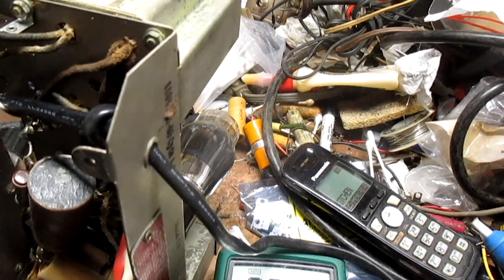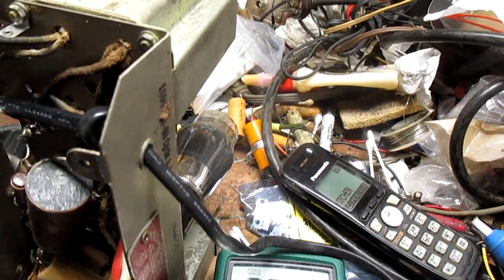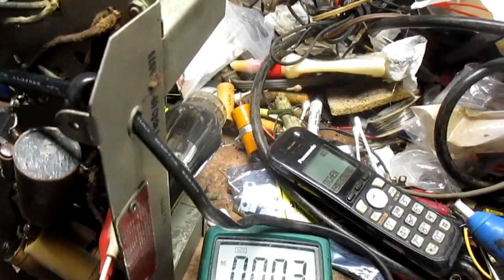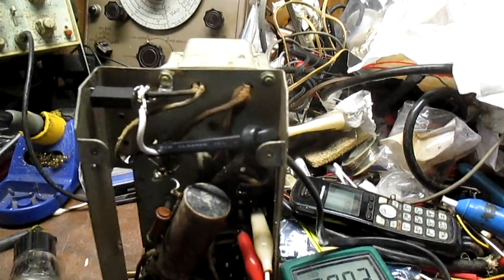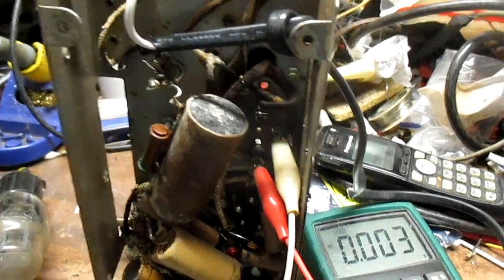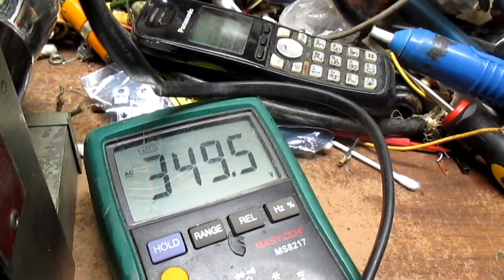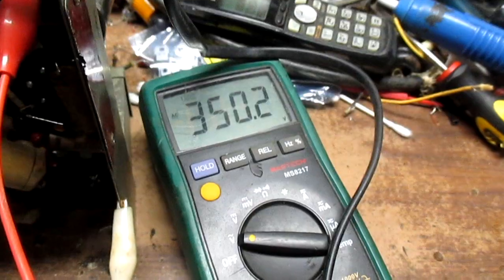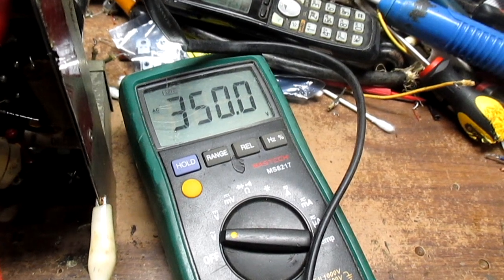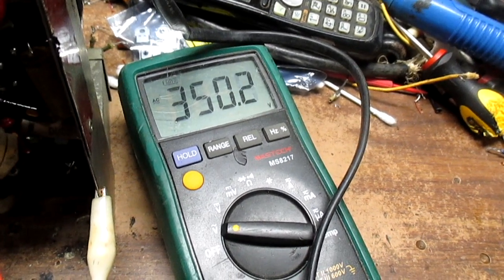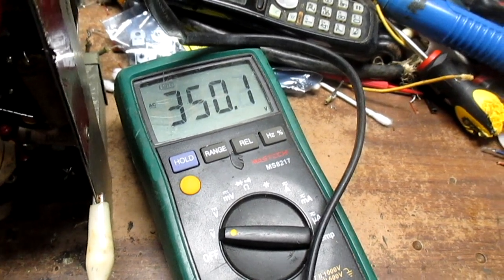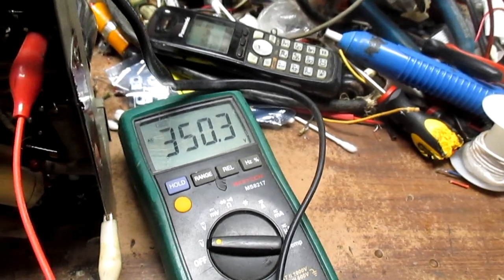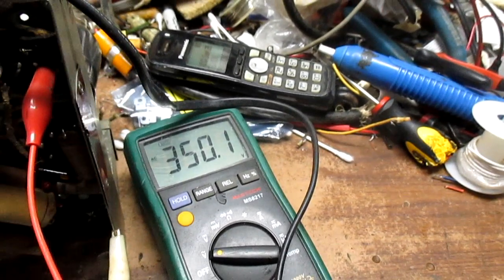Now we're going to check from one side of the high voltage winding to the center tap, and then the other side of the high voltage winding to the center tap. We should have approximately the same voltage on both ends from the center tap. Alright, 349 there, and 350 there. So yep, 349, 350 - the high voltage winding appears to be healthy.